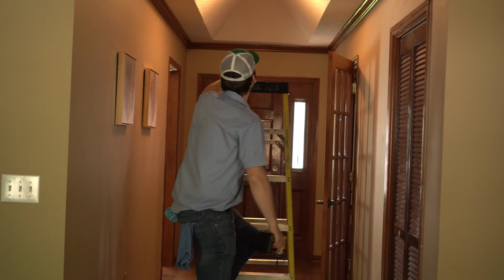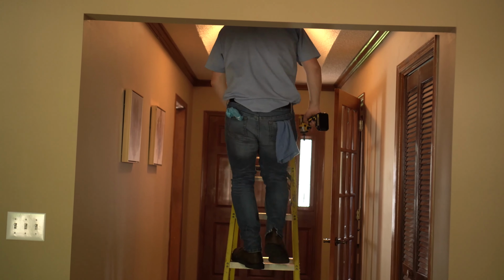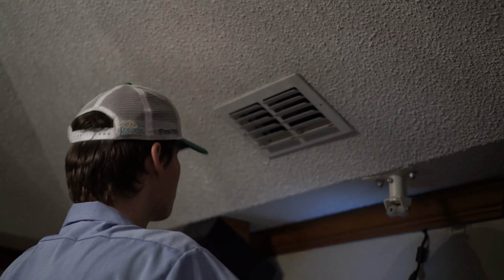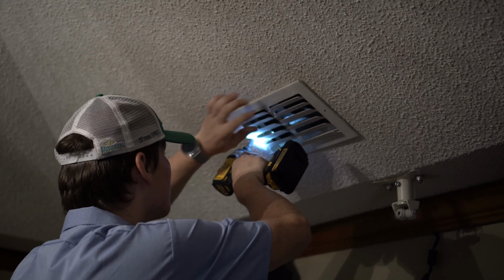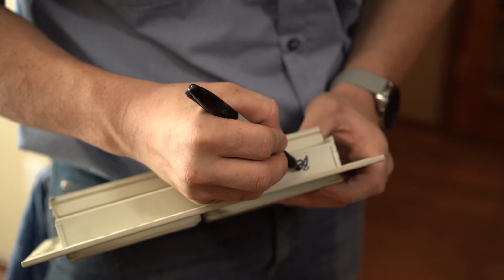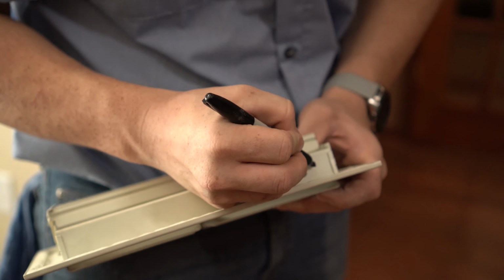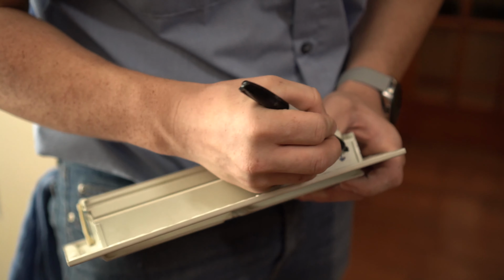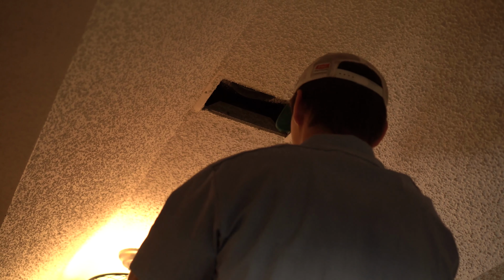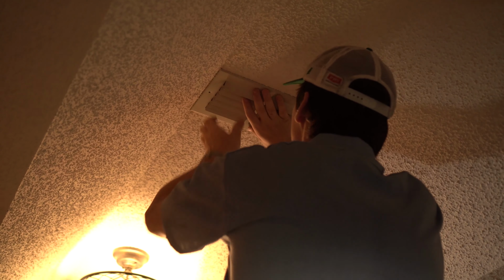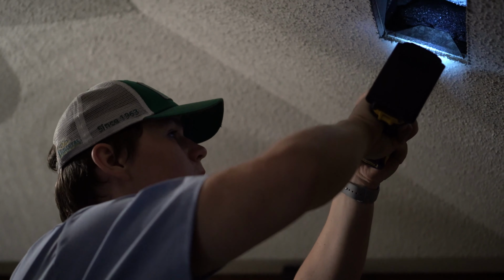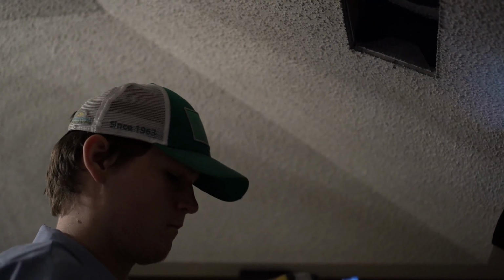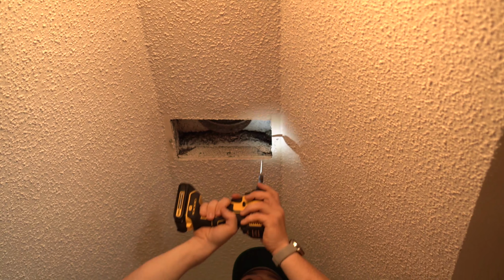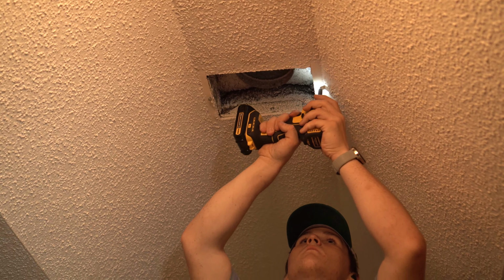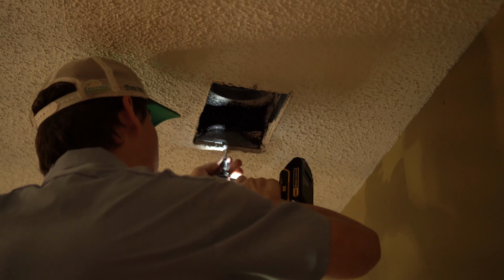Most of the time, vents are aimed towards the outer walls of a home in order to create a proper thermal barrier and are usually aimed to flow across the ceiling for the same thermal protection. Technicians may use a marker to tag locations of particular vents to make sure they go back the same as removed. The sales representative usually advises the client that we will aim them as they should be installed. Return grills are usually installed to prevent unsightly dust to be seen inside the boot areas, so they will normally be towards an inside wall.